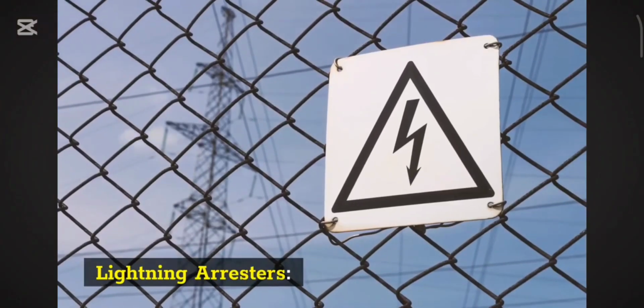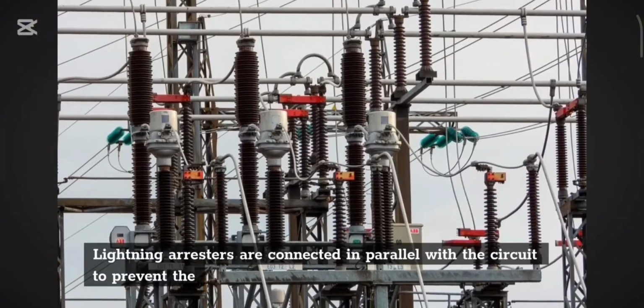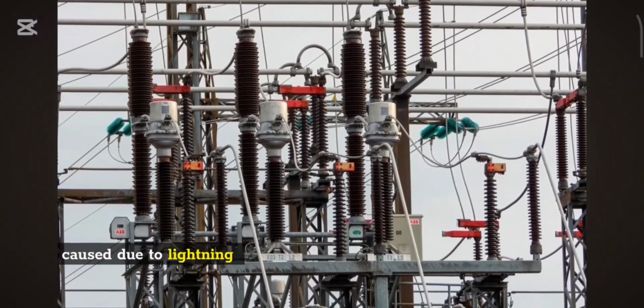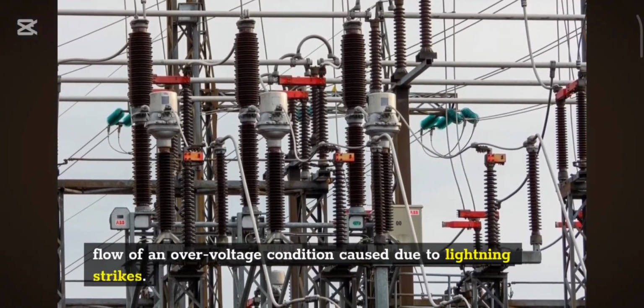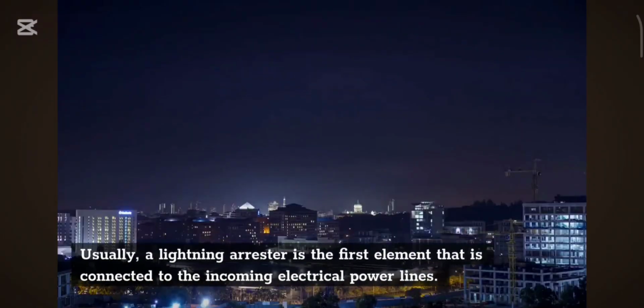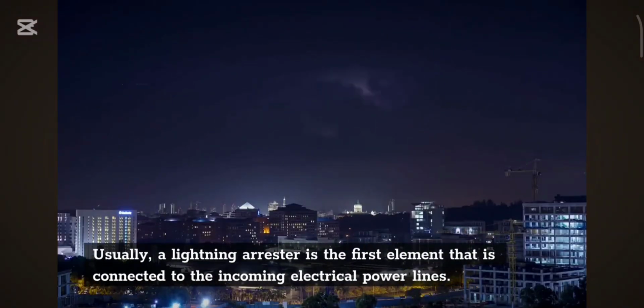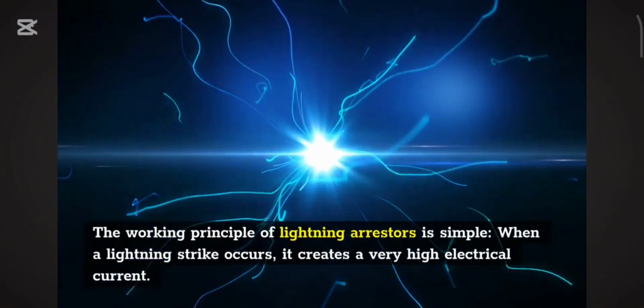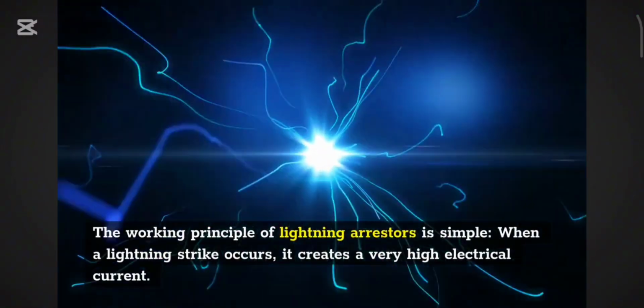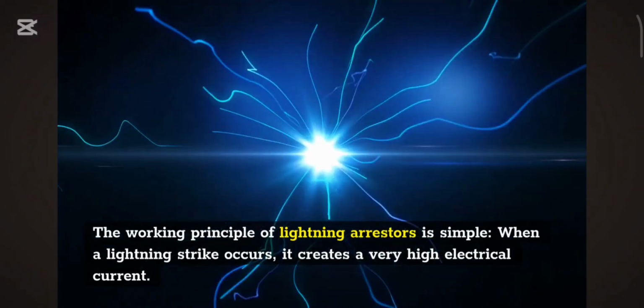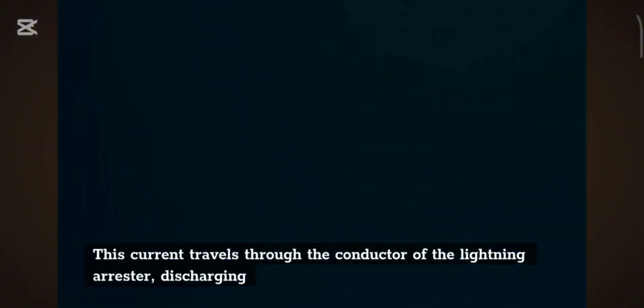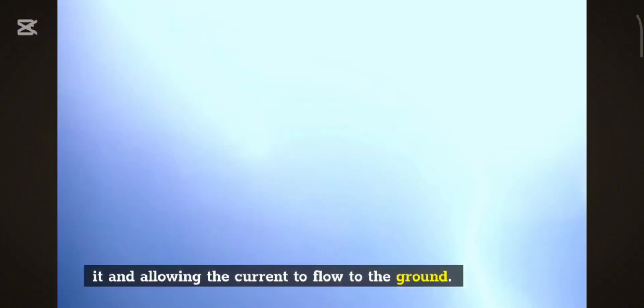Lightning arresters. Lightning arresters are connected in parallel with the circuit to prevent the flow of an over-voltage condition caused due to lightning strikes. Usually, a lightning arrester is the first element that is connected to the incoming electrical power lines. The working principle of lightning arresters is simple. When a lightning strike occurs, it creates a very high electrical current. This current travels through the conductor of the lightning arrester, discharging it and allowing the current to flow to the ground.